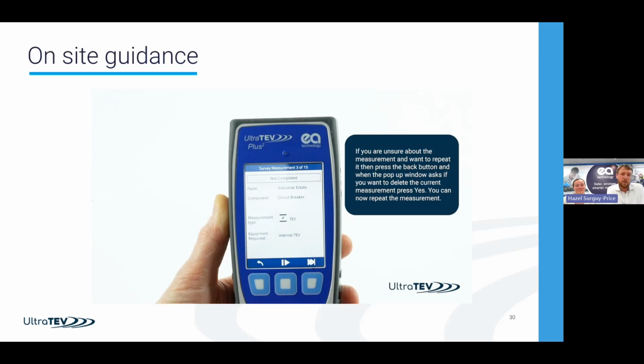You'll see the device now has the capability of having a link to a central system, understanding your asset information, removing any data entry on site - so there's no typing, no errors in that data collection - and allowing the device to take you through what measurements to collect next. In this instance, it's telling you which panel to go to, which accessory or which part of the switchgear, which accessory on the device to use, and what measurement you're going to take.